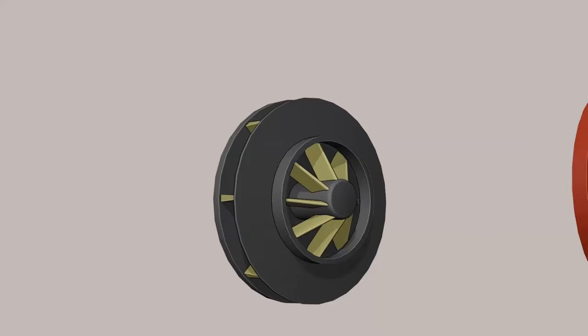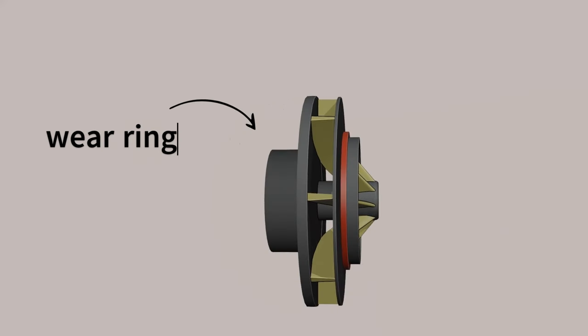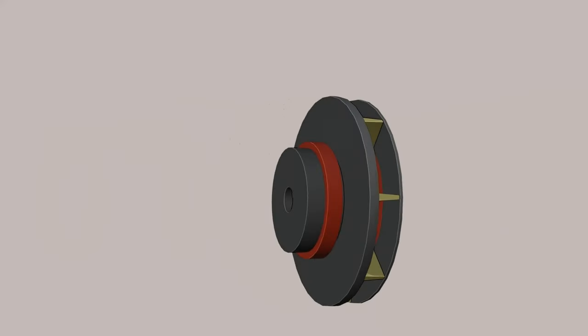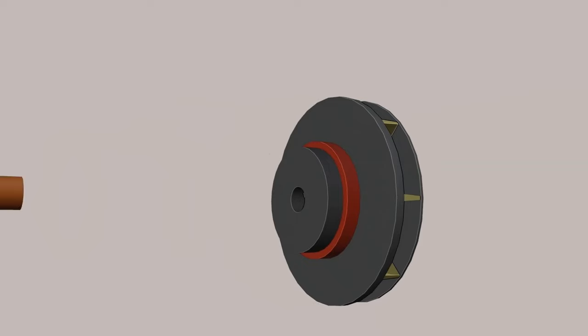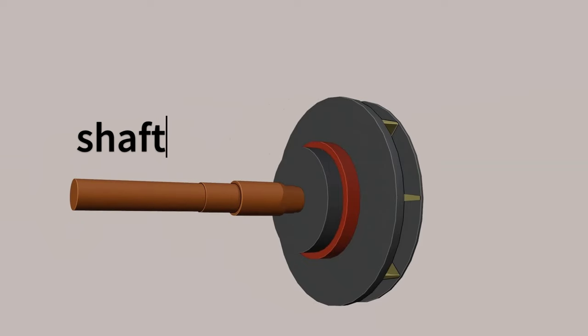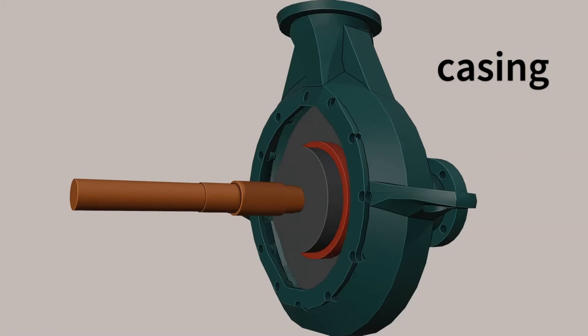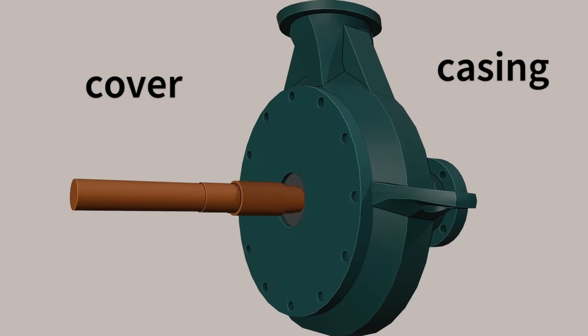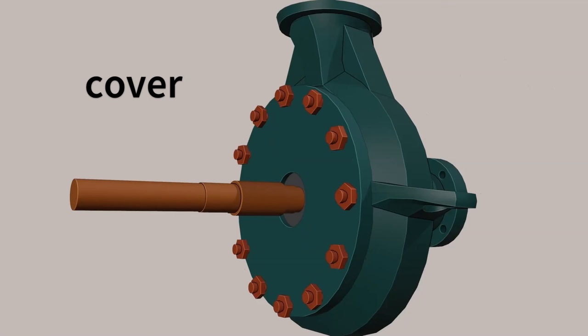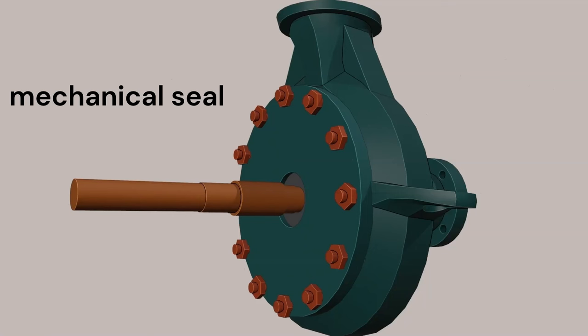Wear rings are placed on both sides of the impeller to reduce wearing. The shaft has the impeller placed on one end using a key guide to transfer rotation from the motor. The casing and cover are placed on both sides of the impeller to create an enclosed pressure chamber. A mechanical seal is used to avoid leakage from the chamber to the atmosphere.